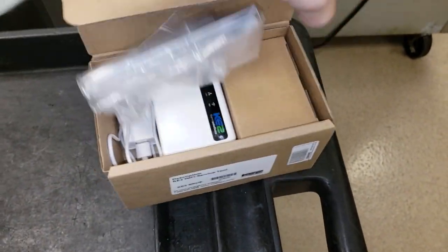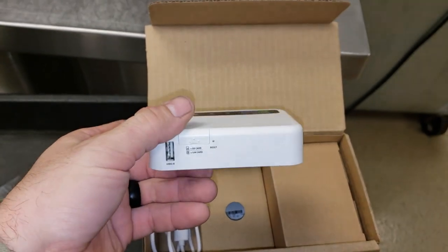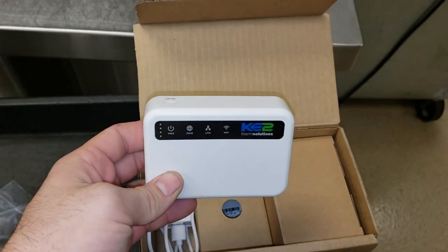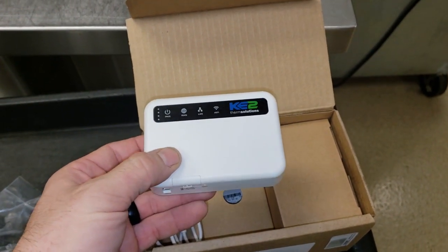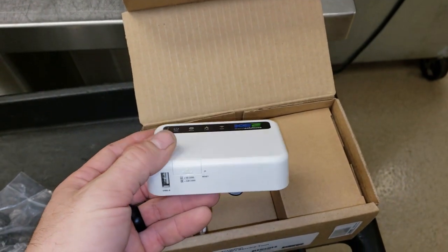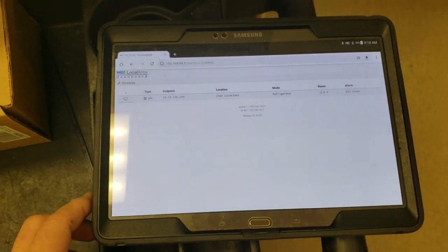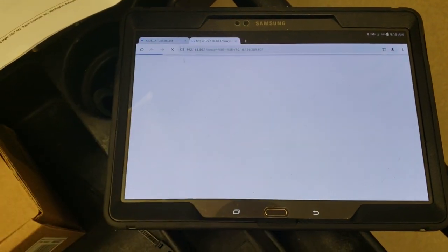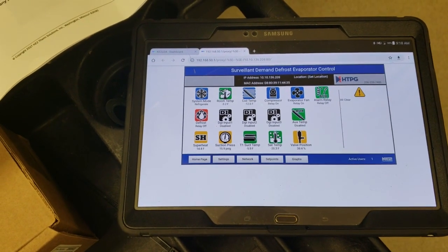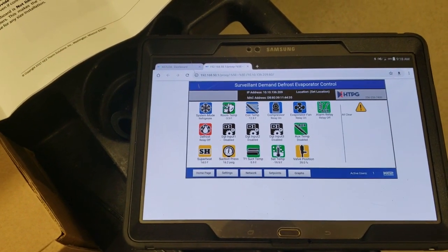So we're going to see how this thing works. The Wi-Fi service tool gives me wireless access via my smartphone or tablet, and I don't have to plug the ethernet cable into the KE2 Therm controller anymore — supposedly. So we're going to try it out. I plug the Wi-Fi service tool into the ethernet port of the controller, simply enter the IP address, and here we go — we have a full display allowing us to see everything we need to see.